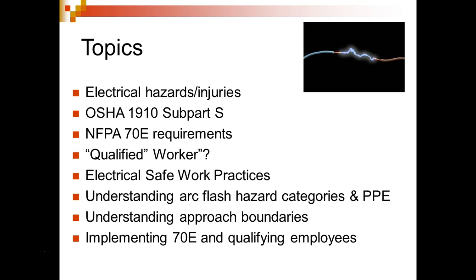Also understanding arc flash hazards, categories of PPE. Everybody understand what PPE is now? Safe approach boundaries. Anything above 50 volts requires an energy available or energy standard analysis - how much energy is available. We might have 120 volts protected by a 100 amp breaker, which would have more stringent safeguards than 400 volts protected with a half amp fast-blow breaker. So they do an energy capabilities analysis on your system, and this determines the PPE you have to wear, and also the boundaries. We have different safe approach boundaries in different places, and the closer you get to high energy, the more types of PPE you have to wear.